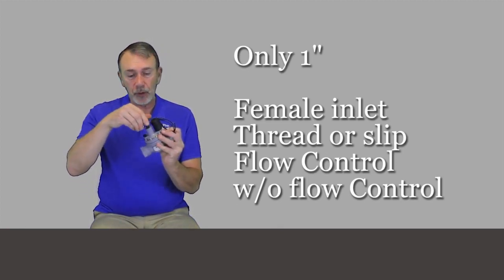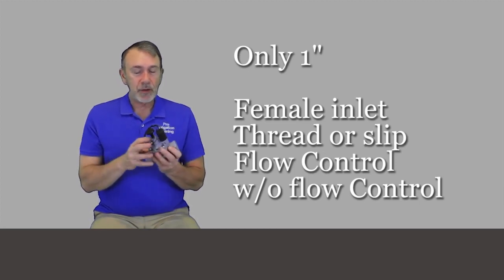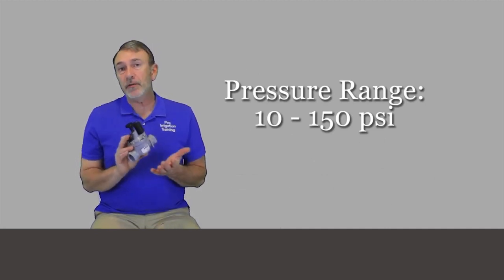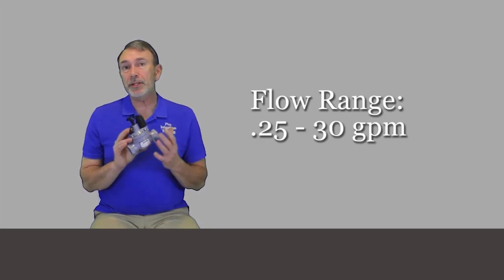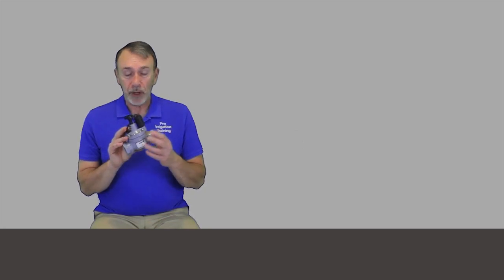Obviously, this one has a flow control on it. The specs on this for the operating pressure range is 10 to 150 PSI. The flow range on it is 0.25 through 30 gallons per minute. It runs really good at low flows—0.25 is one-fourth of a gallon per minute, so it's a great valve to use with low flow drip systems.